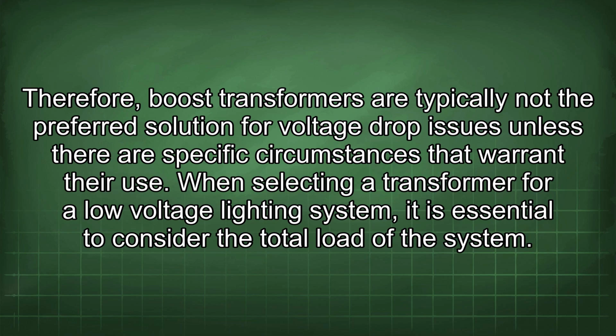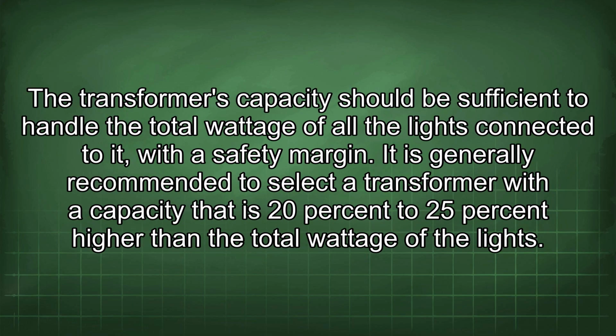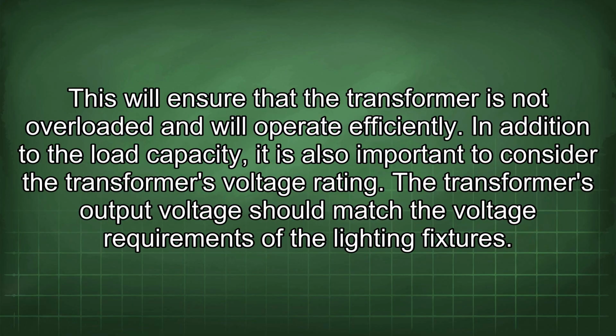When selecting a transformer for a low-voltage lighting system, it is essential to consider the total load of the system. The transformer's capacity should be sufficient to handle the total wattage of all the lights connected to it, with a safety margin. It is generally recommended to select a transformer with a capacity that is 20% to 25% higher than the total wattage of the lights. This will ensure that the transformer is not overloaded and will operate efficiently.